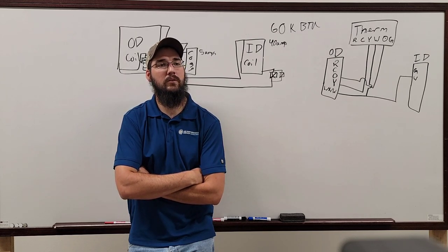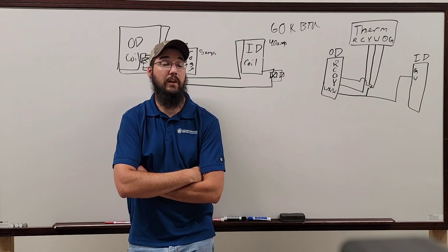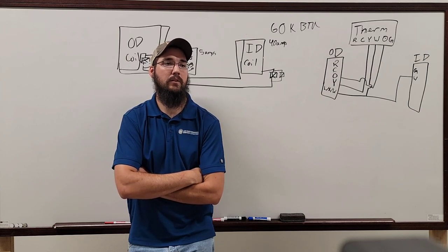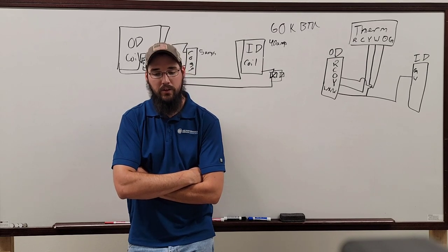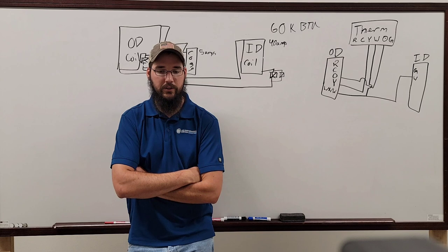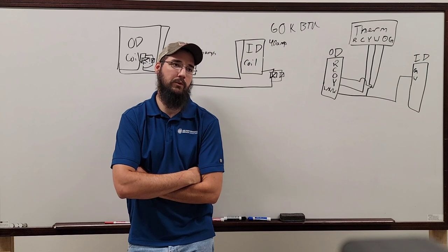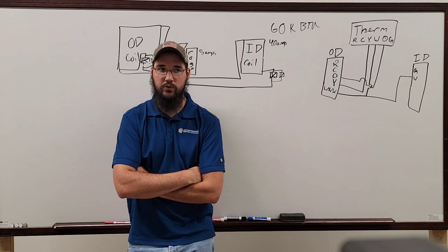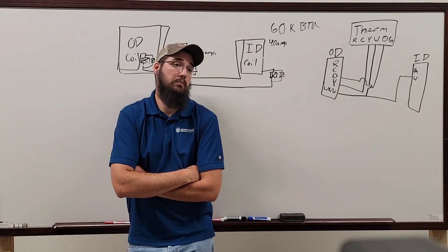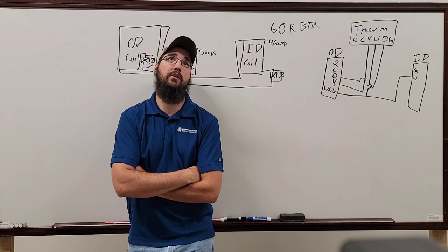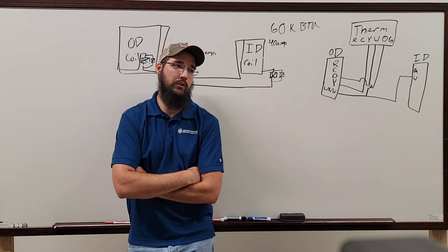Basically, everything applies the same for water source heat pumps. It's just a matter of transferring the different mediums. Yes. With our defrost, it's not relevant because it's not going to freeze. Yeah, that is true. We didn't touch on it. I'm actually glad you brought it up because I had forgotten about it. Water source heat pumps operate at a completely different sequence of operation. There's no defrost or anything needed. And that's where a boiler system comes in. That's one of the things that a lot of engineers really struggle to understand too, is you have to have a functioning boiler with a water source heat pump system.